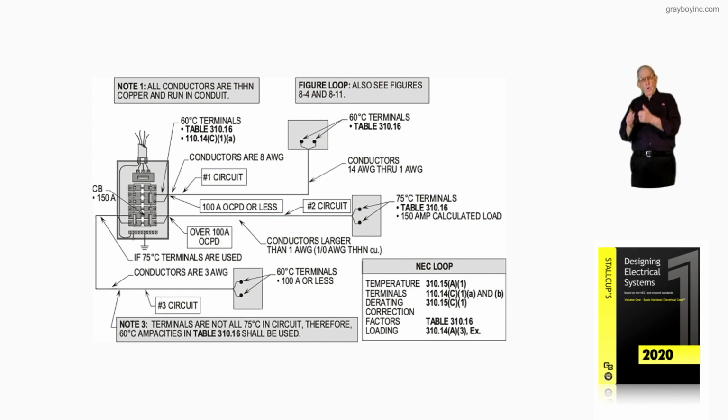And then when you're over 100 amps, you really have to get with the inspector on this, because they may require, if it's over a 100 amp device, 1/0 wire or larger. This is a call of the authority having jurisdiction, and a lot of them will give you the grace and let you size according to whatever you calculate. But others may not.